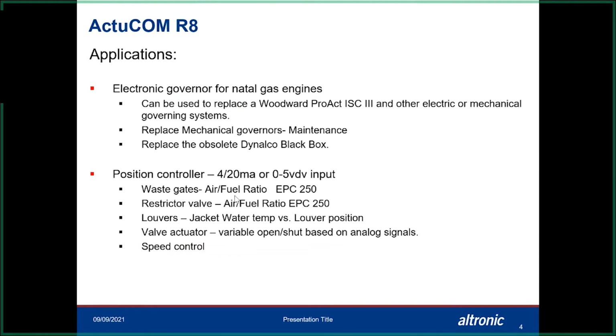Also on here I put restrictor valve. That's the same application, just a different way of looking at it. Wastegate wastes air, restrictor valve restricts the air going to the engine. We have many on engines controlling small louvers on like 3300 Cats. They're controlling those louvers basically off their jacket water temperature, and they're working very, very well on that application.